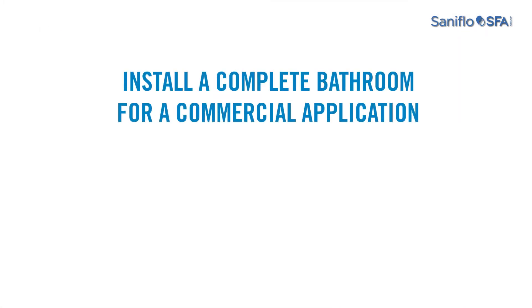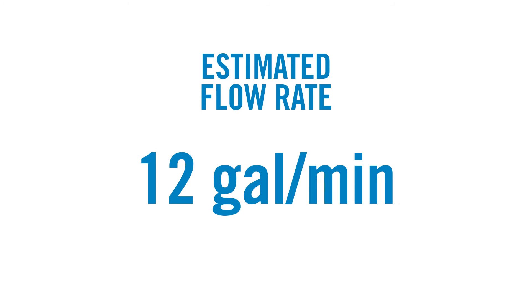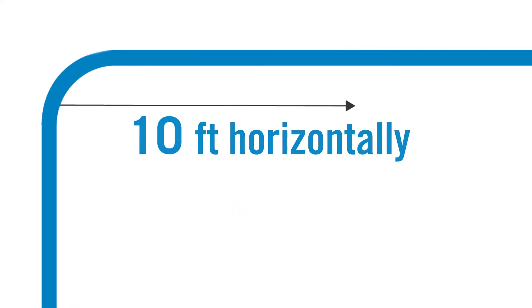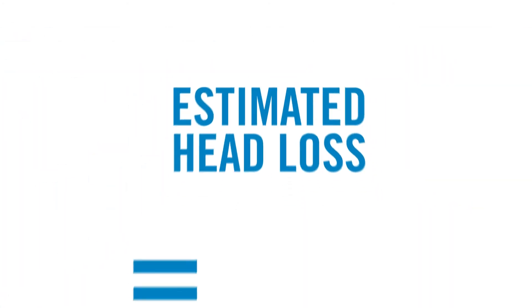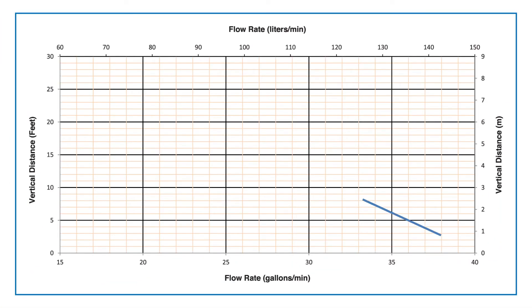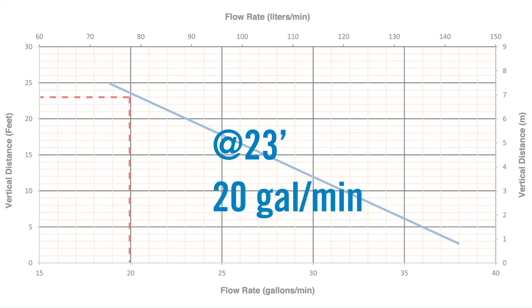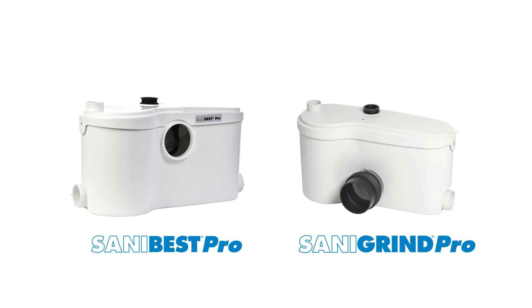Here's an example. If you're looking to install a complete bathroom for a commercial application with a toilet, a shower, and two sinks, the estimated flow rate is 12 gallons per minute. Your unit will have to pump up 20 feet vertically and 10 feet horizontally using a three-quarter inch pipe without a gravity slope. This means the estimated head loss is 23 feet. The system would need to pump at least 12 gallons per minute at a total of 23 feet of head. By reviewing the pump curve, it shows that at 23 feet the pump will discharge 20 gallons per minute, which satisfies our requirement. Both the Sanibest Pro and the Sanigrind Pro are perfect systems for this application.